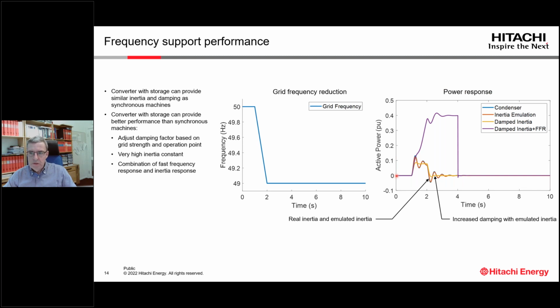So the active power injection from the synchronous condenser is 0 when the frequency is constant, and then at 1 second we go up with the power, and we get this injected power. And then at 2 seconds the frequency is constant again, and then we go down with the power to 0 here. Now we could emulate this with the converter with the storage, and that is the red curve. And you could see we could follow exactly what the synchronous condenser can do. But we could see here that we have oscillations, and that is not so good. And of course, with the controller, we could change the parameters in it, and then we could damp more, and then we could get to this yellow curve here that looks much better.